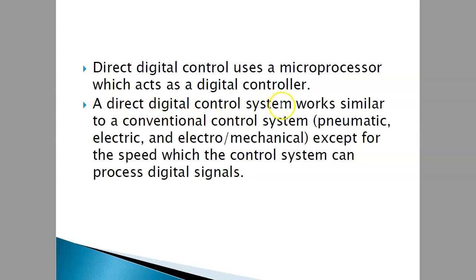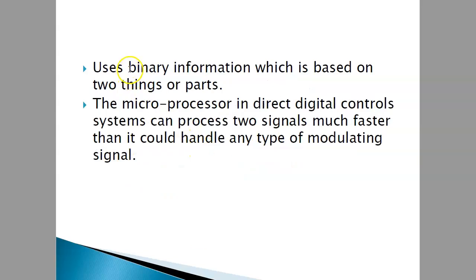Direct digital control system works similar to the conventional control system, pneumatic, electronic, and electromechanical, except the speed of this control system is faster. It uses binary information which is based on two parts. Binary is 1 or 0, 1, 0, 1, 0. The microprocessor also could control two signals much faster than could be handled by other types of modulating signal.